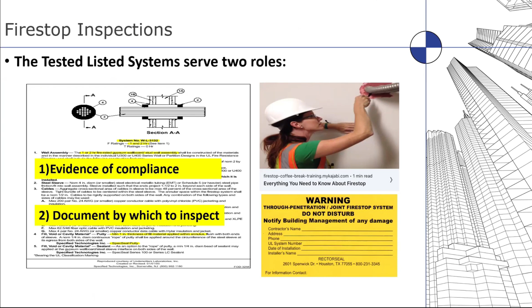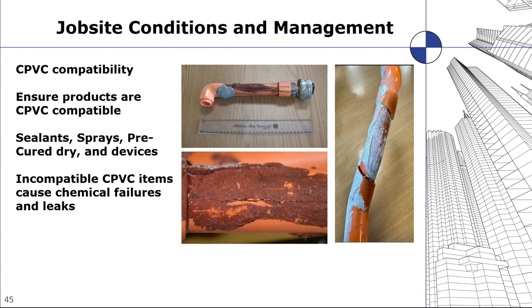In this case, that orange pipe is a CPVC sprinkler pipe. That material can be affected by different kinds of chemicals, and in some cases the chemical reaction can cause problems - it can create pinholes or cracks and have a negative chemical reaction, creating a breach in the pipe, which loses air pressure, meaning the sprinkler system no longer works. So one of the things inspectors look for is to make sure the material is compatible with the construction.